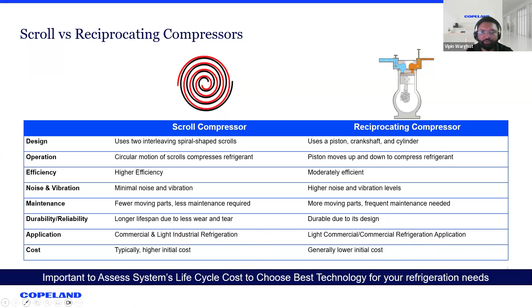I want to take you through a couple of more features of the scroll, which is accompanied with the variable speed technology. So basically, if you have a huge gap between supply and demand, and there are variations in voltage, current, and frequency of the driving power which is driving your refrigeration system, that's where variable speed technology plays a wider role. There's a variable speed drive which is controlled by the controller of the cold chain system, and that is providing the signal for modulating the drive and ultimately driving the compressors to produce the refrigeration for the system.